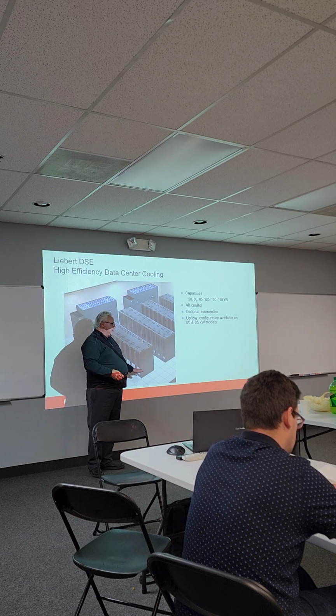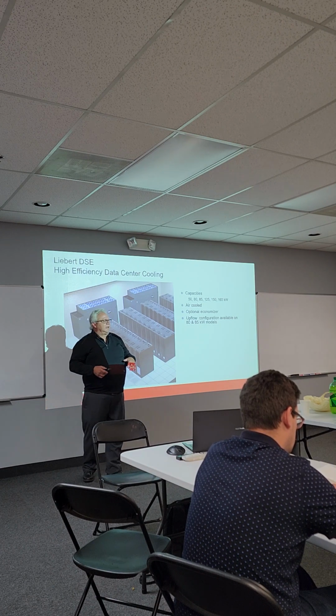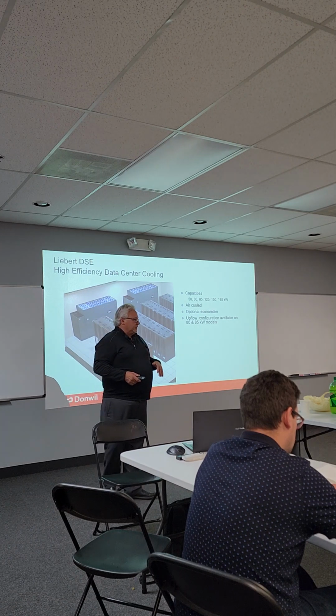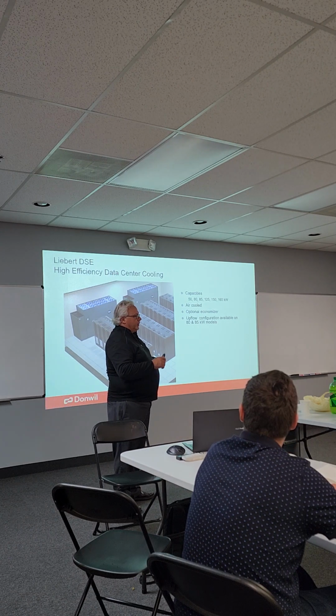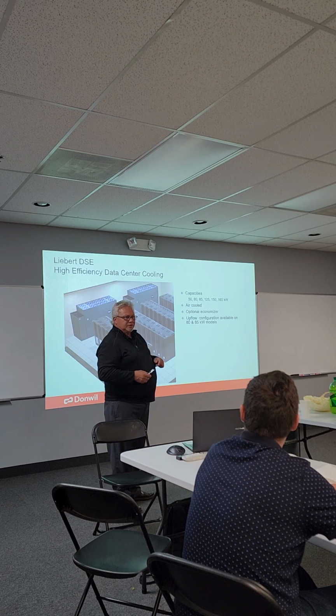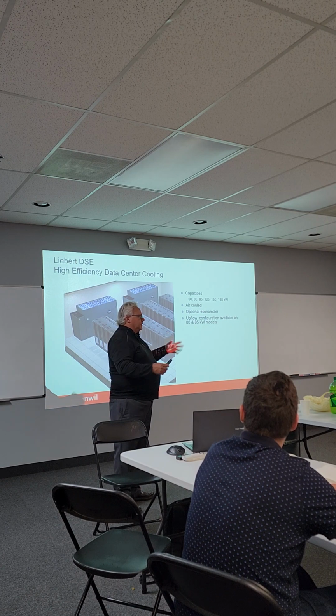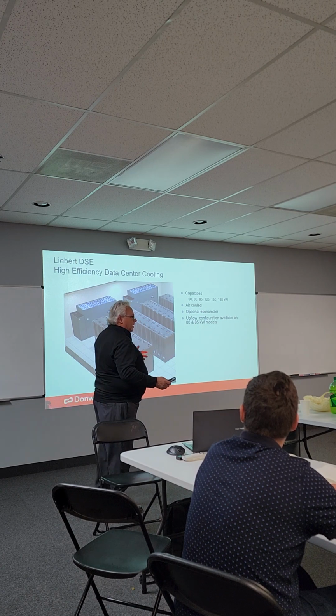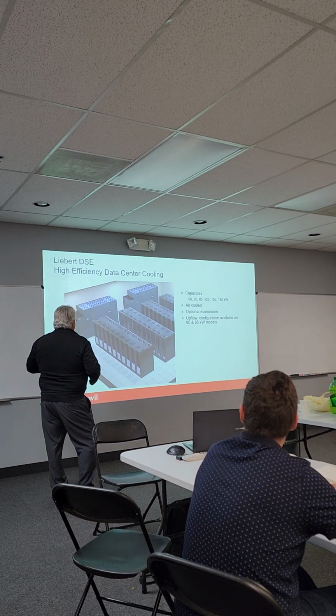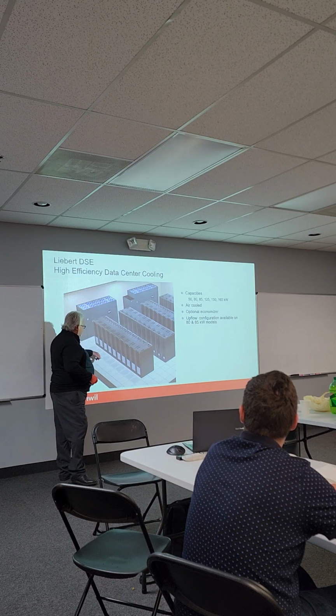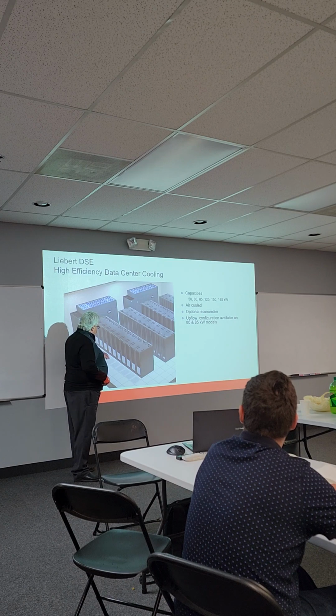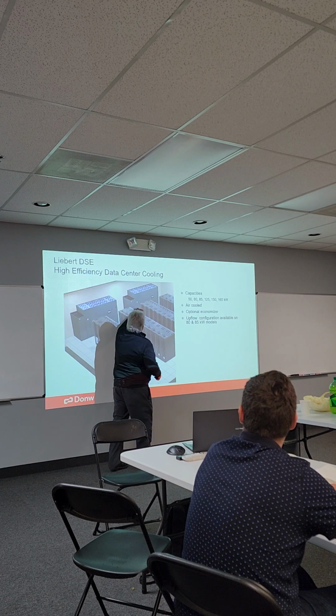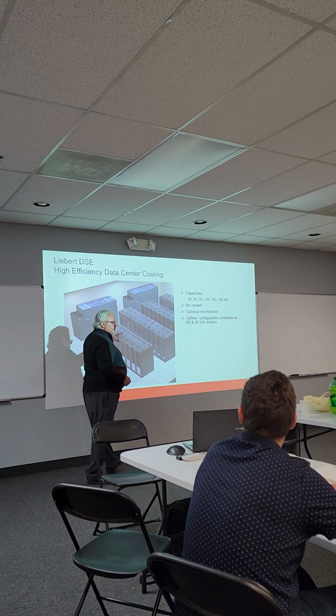And the reason I bring that up is that a customer says, I need 20 tons of air conditioning. We don't do any investigation. We put 20 tons of air conditioning in, and we still have the same problem that we had before. We're just throwing 20 tons of air conditioning at it. We're not solving the problem. The problem doesn't go away. The problem, in this case, is this unit's sucking back cold air along with the hot air, and the unit satisfies.